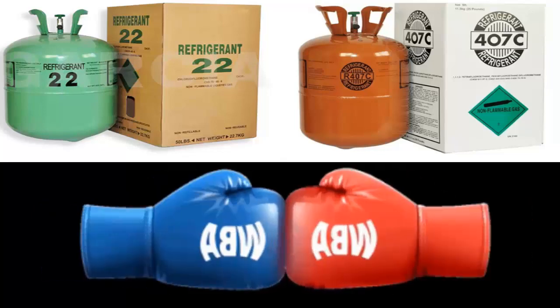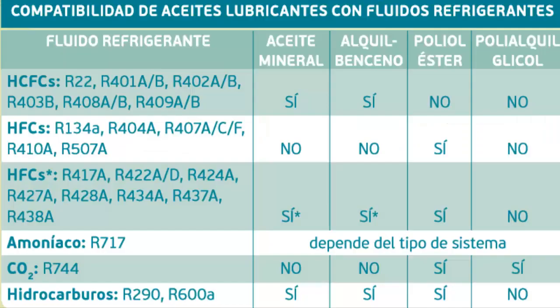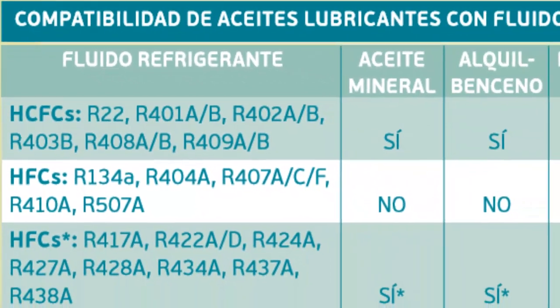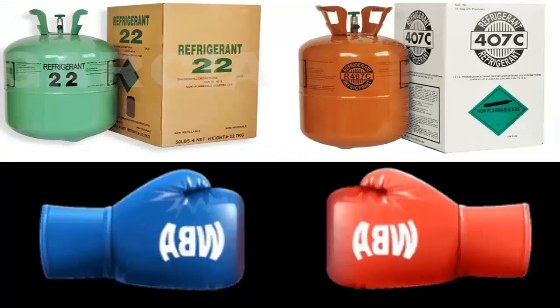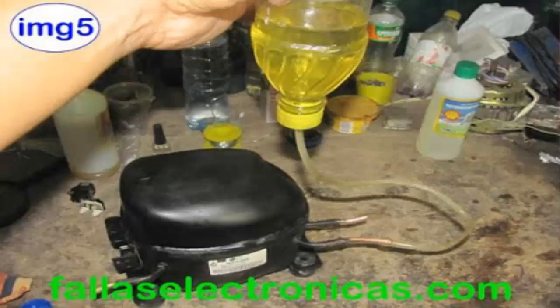Another significant difference between the two gases is their compatibility with different types of oil. R-22 is compatible with mineral oil and alkylbenzene, but not with PoE oil. On the other hand, R-407C is only compatible with PoE oil. This implies that when replacing R-22 with R-407C in air conditioning equipment, it is necessary to change the oil due to the differences in gas properties and lubrication requirements.